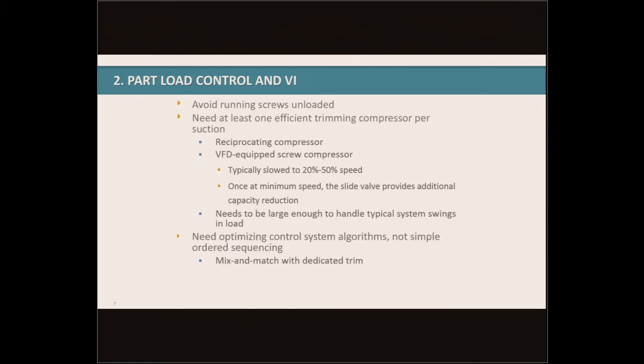The second point is part load control and VI. The common rule of thumb is you never want to run a screw compressor unloaded when you can avoid it. Compressors are most efficient running at 100% load and least efficient when running part load or severely part loaded. So anything we can do to keep compressors operating fully loaded will have positive benefits.